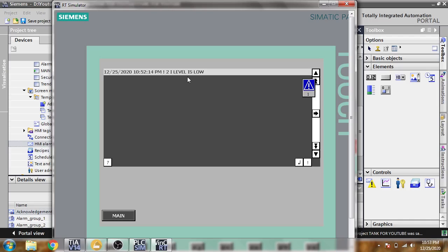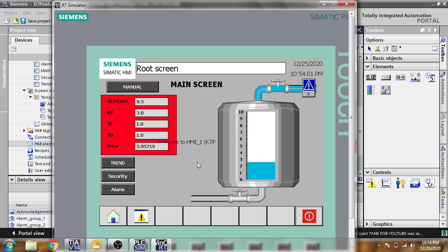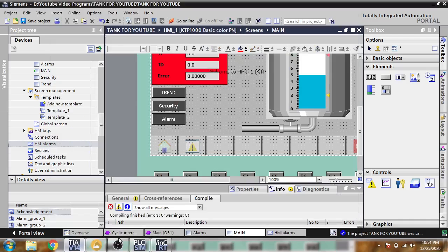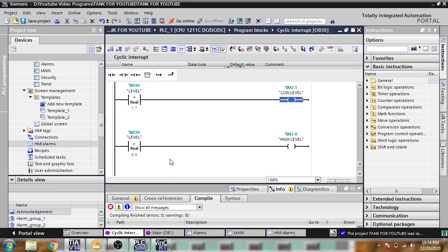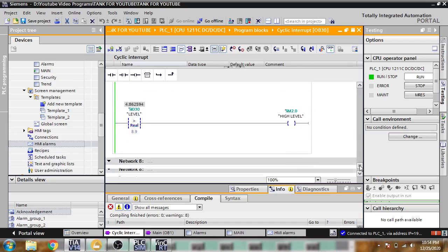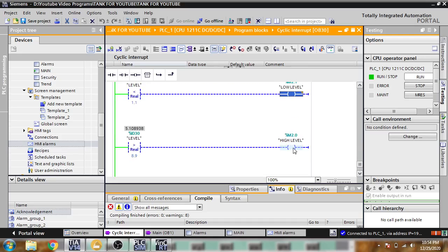One alarm is low. The PLC alarm is going because our level reaches our PLC tag. I'm going to check that in our cyclic interrupt. You will see our low level bit is open — that's why it is creating alarms.